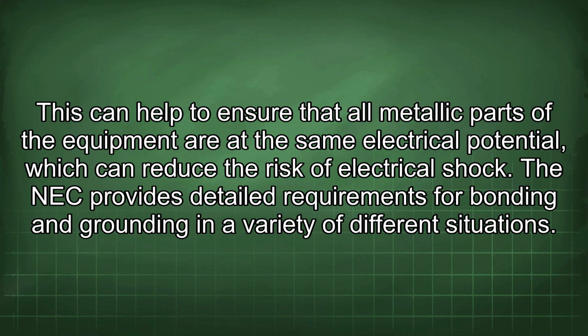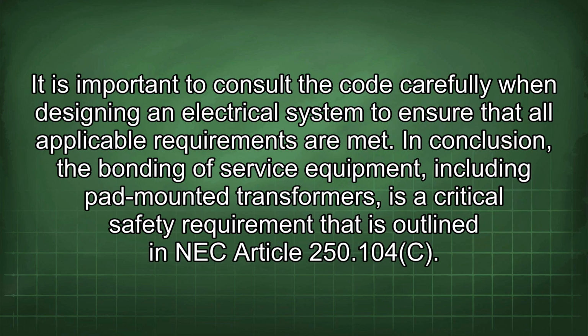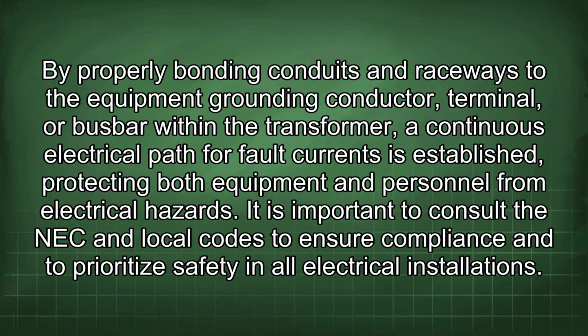The NEC provides detailed requirements for bonding and grounding in a variety of different situations. It is important to consult the code carefully when designing an electrical system to ensure that all applicable requirements are met. In conclusion, the bonding of service equipment, including pad-mounted transformers, is a critical safety requirement that is outlined in NEC Article 250.104(C). By properly bonding conduits and raceways to the equipment grounding conductor, terminal, or busbar within the transformer, a continuous electrical path for fault currents is established, protecting both equipment and personnel from electrical hazards. It is important to consult the NEC and local codes to ensure compliance and to prioritize safety in all electrical installations.